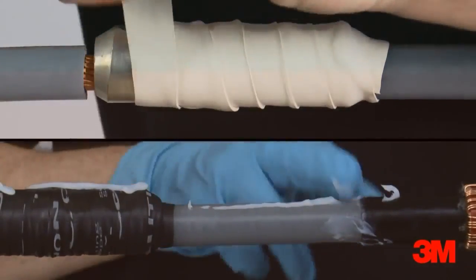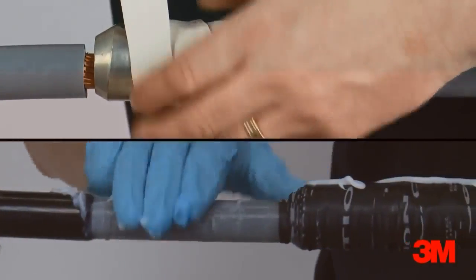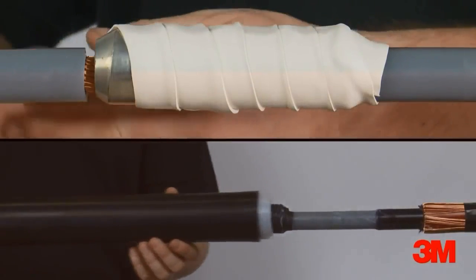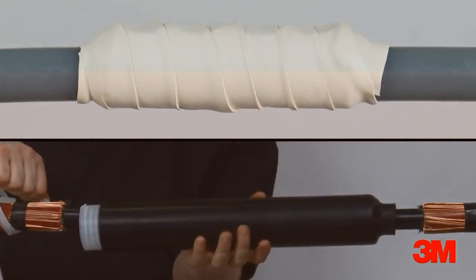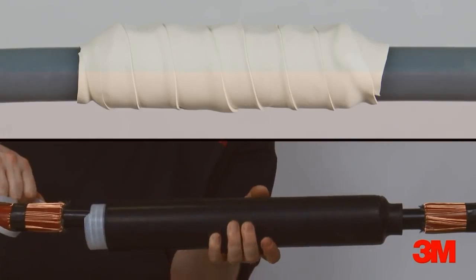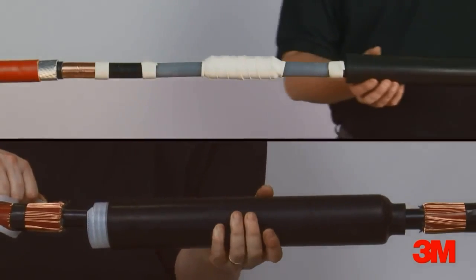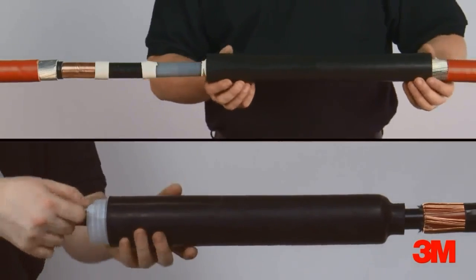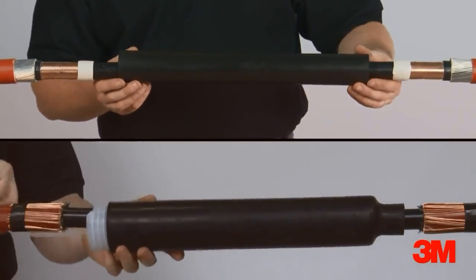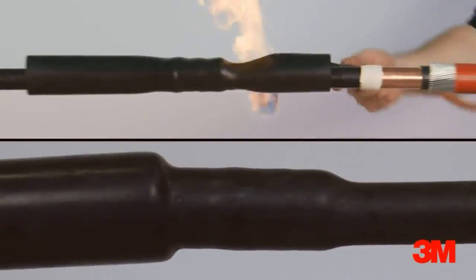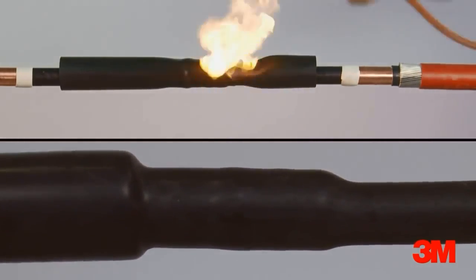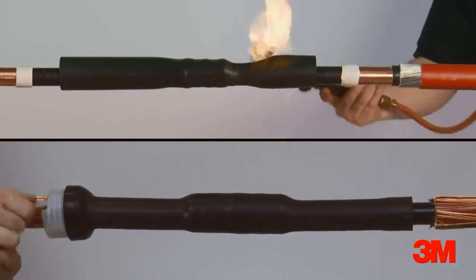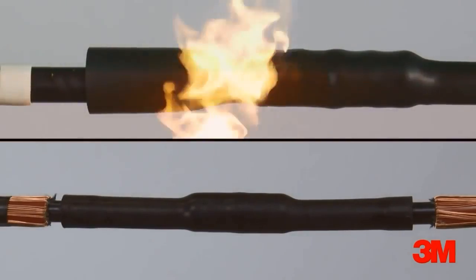Compared to heat shrink alternatives, there is less chance of damaging XLPE cable material, less room for jointer error, and no cooling time needed before energizing. It is easier to use in enclosed areas, and there is no requirement for special site permits. In a number of applications, time-saving benefits of cold shrink can be considerable, thus lowering the overall installation cost.